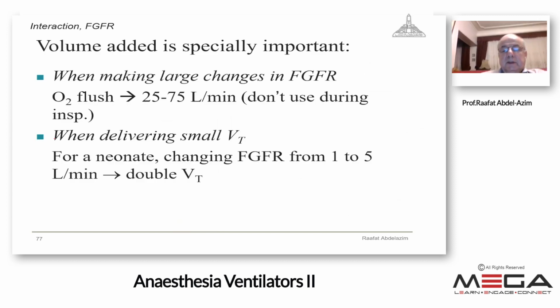The volume added is important. It is more important when we make large changes in fresh gas flow rate. These large changes can be obtained, for example, if we press the oxygen flush during mechanical ventilation. Always don't initiate the oxygen flush during mechanical ventilation, especially during the inspiratory time. It will add much to the tidal volume. The flow rate during activation of the oxygen flush may reach up to 75 liters per minute.